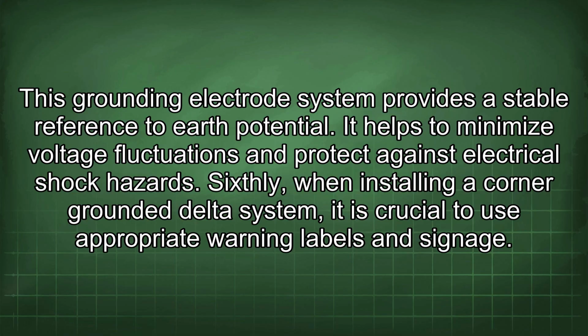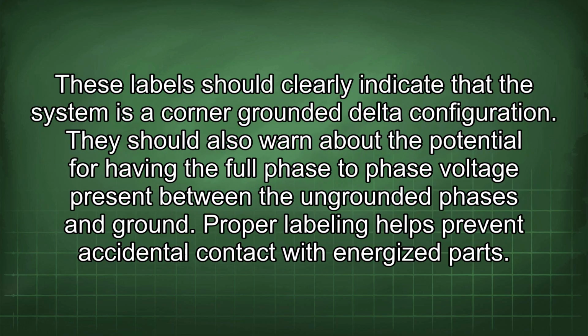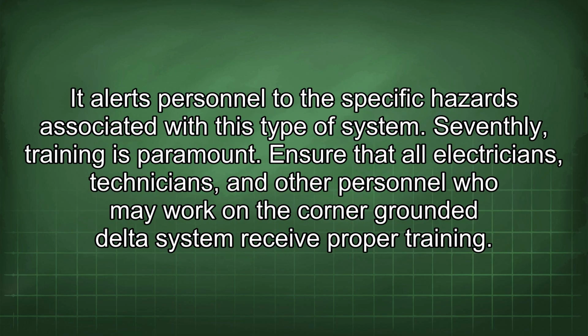Sixthly, when installing a corner-grounded delta system, it is crucial to use appropriate warning labels and signage. These labels should clearly indicate that the system is a corner-grounded delta configuration. They should also warn about the potential for having the full phase-to-phase voltage present between the ungrounded phases and ground. Proper labeling helps prevent accidental contact with energized parts. It alerts personnel to the specific hazards associated with this type of system.